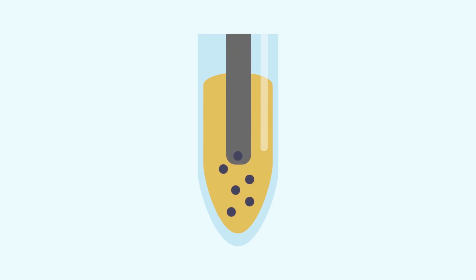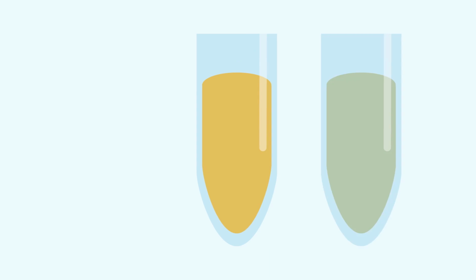Particle movers attract magnetic beads to a magnetic rod. The beads are moved with the rods to wells pre-filled with extraction reagents. When the beads reach a well, magnetization stops and the beads are released. Mixing disperses the beads. Then the rod is remagnetized and the beads are moved to another well.